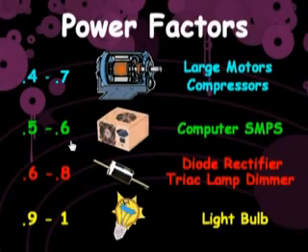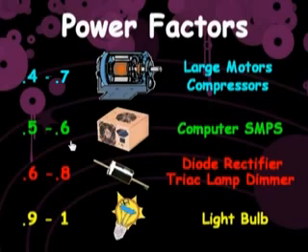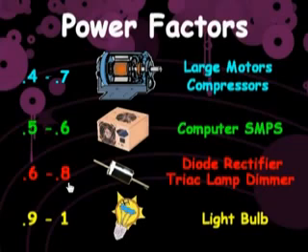A power factor of 0.6 means that 60% of the amps flowing in the electrical wires produce watts that develop operating DC voltages and DC current for this computer power supply, while 40% of the amps are harmonic currents that produce no watts. A power factor of 0.8 means that 80% of the amps produce watts for this lamp dimmer and light bulb, while 20% of the amps are harmonic currents that produce no watts.